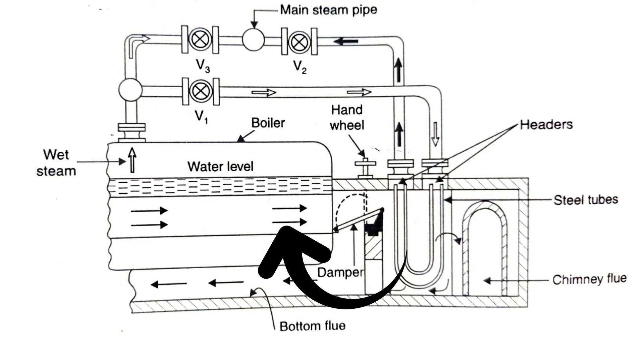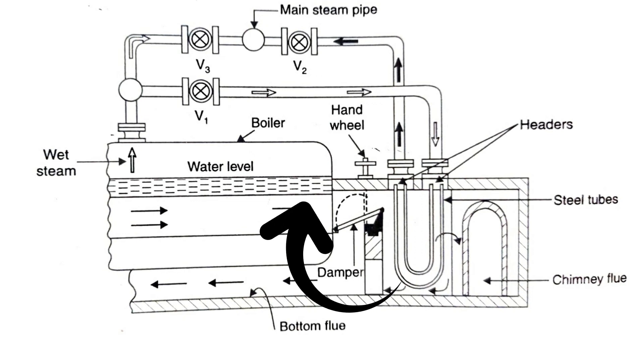A balance damper is provided in the superheater to prevent overheating of the superheater tubes. This damper is operated by a handle — by turning the damper upward into the vertical position, the gases pass directly into the bottom flue without passing over the superheater tubes. By placing the damper in an intermediate position, part of the gases will go over the superheater tubes and the remaining will pass directly to the bottom flue, allowing varying degrees of superheat to be obtained.